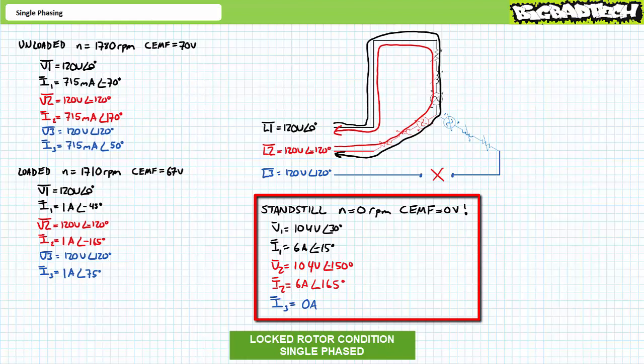If this motor was serviced by an overload relay set at a rated current of one amp, it would quickly signal an overload condition and open the primary contacts to break the circuit. Lacking overload protection, the remaining windings would be quickly damaged or destroyed. This is most assuredly not how you want to operate this motor.